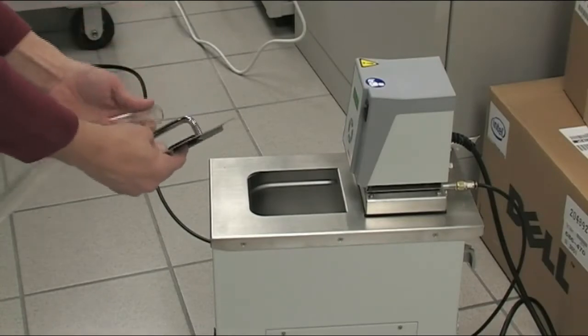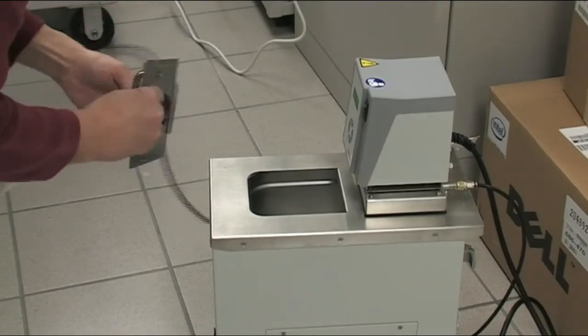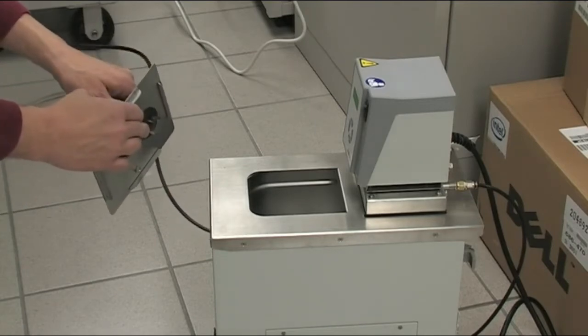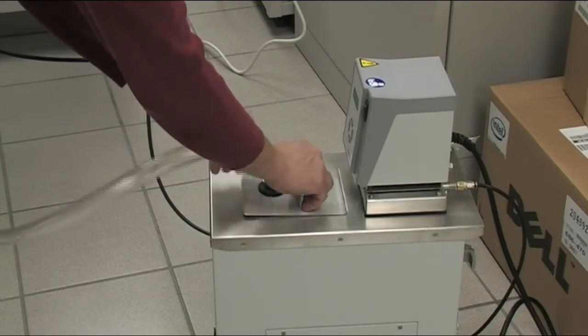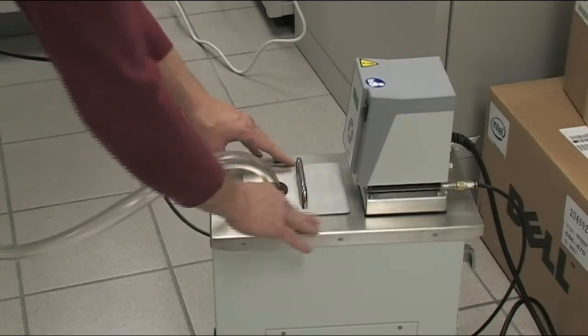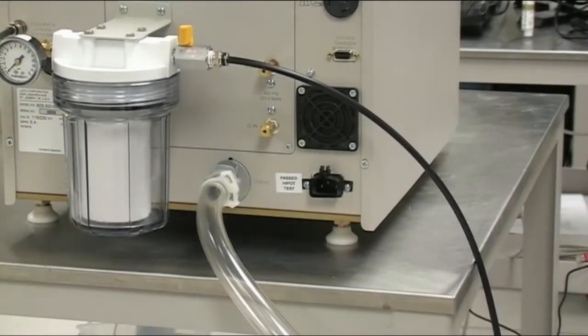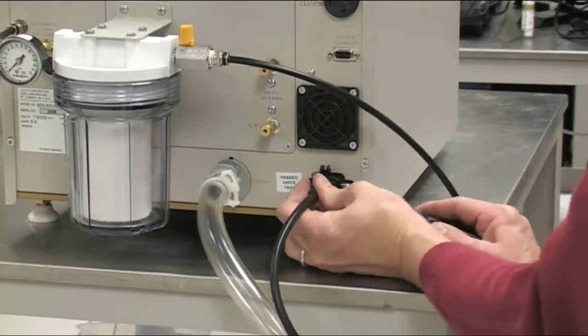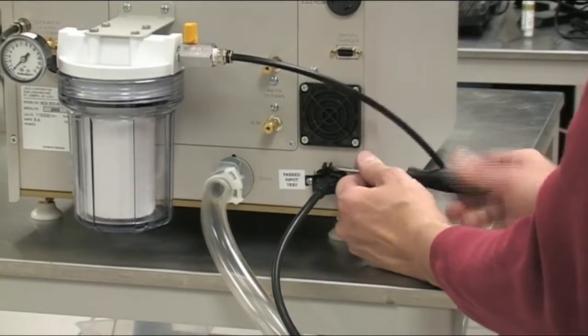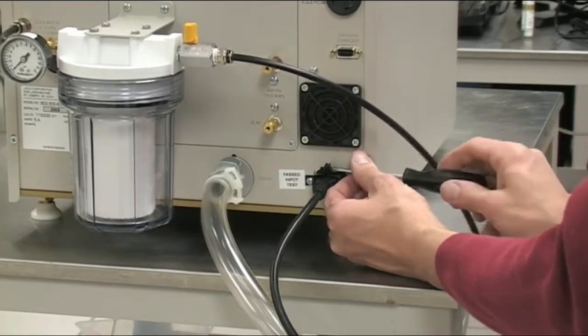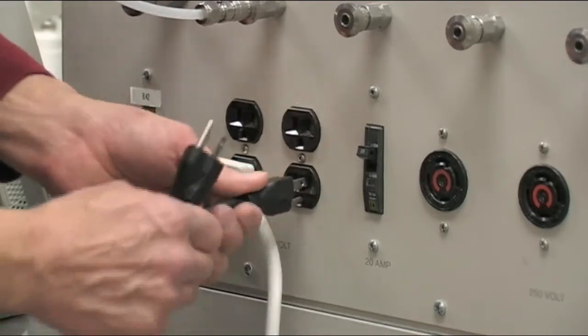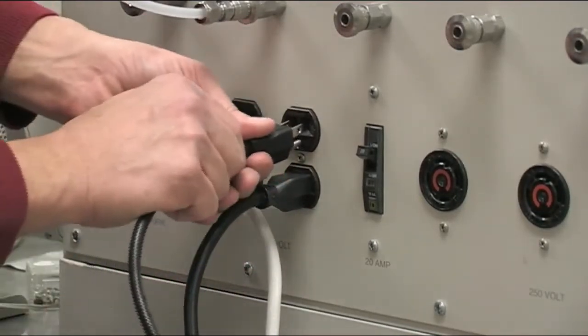The next thing you want to do is install the drain line through the cover. You want to go through approximately anywhere from a 1/2 inch to an inch in through the cover, and then put the cover on top of the machine. The next thing you want to do is attach the power cord to the instrument. The instrument has the capability of using either 115 or 230 volts. It is an auto switching transformer in it. Plug in firmly and then tighten the hold down screw. Next thing you want to do is plug in both the chiller power line and the instrument power line.